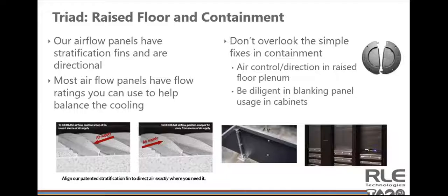For example, one of the data centers I worked at previously, we shaved $70,000 a year in operating costs just by cleaning up and moving towards a hot aisle containment solution there. And you'll also want to develop a plan. You don't want to just kind of willy-nilly go in and start trying to fix things. Coming up with a plan that's focused on containment and that best fits your space is what I have found to be the best starting block.